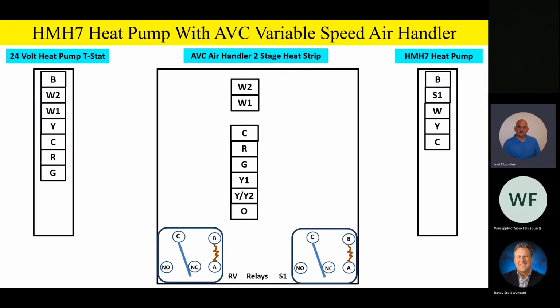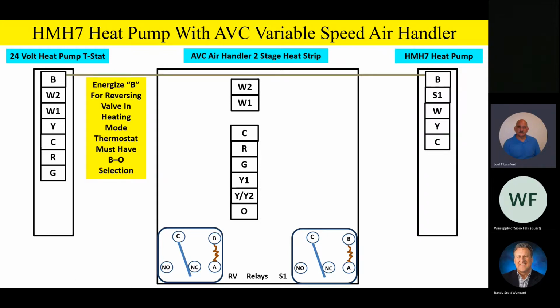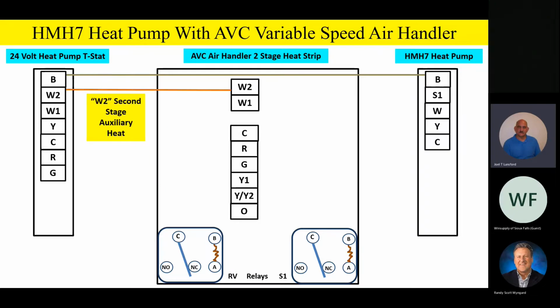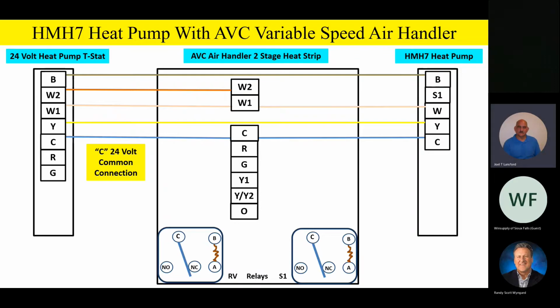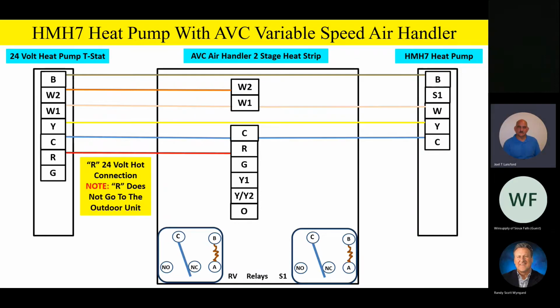Now, down below, you'll notice I've got 2 relays down there, the RV relay and the S1 relay on the little graphic. So just like we had before, fellas, B is going to energize that reversing valve in the heating mode of operation. That does not change. And if you have like a 2-stage heat strip, W2 will be your 2nd stage auxiliary heat. W1 is going to be your 1st stage auxiliary heat, and that's going to carry on the outside, so we can bring some heat strip on during defrost on that W1 call. Y terminal is going to go outside just like before, as well as C 24-volt common. R is going to hook up just like it did before, and it does not go outside.